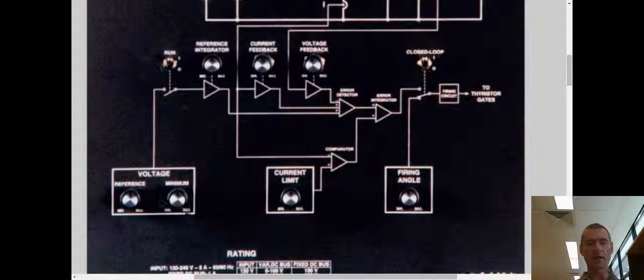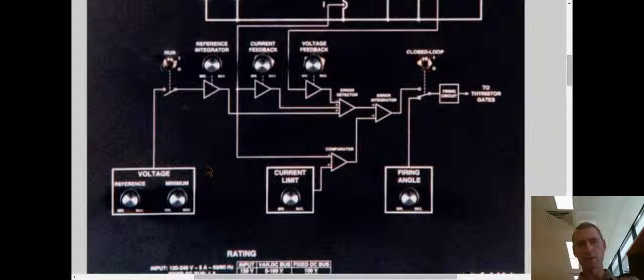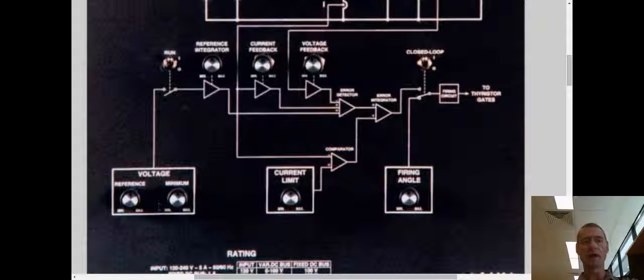And minimum just means the minimum voltage that's going into this control circuit or the minimum speed that that voltage reference can go down to. So the voltage reference goes from the minimum set here up to a maximum. The run selector, of course, if it's set to zero, then that doesn't get inputted into the control circuit. Otherwise, you switch to one, you get that signal coming in.